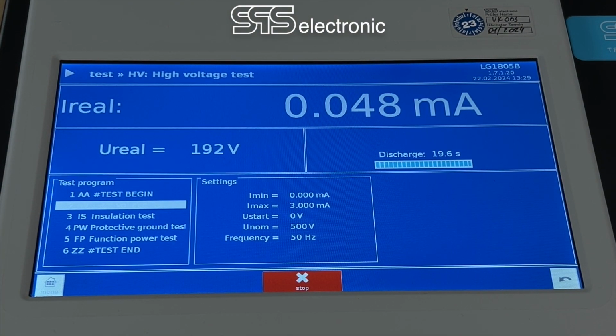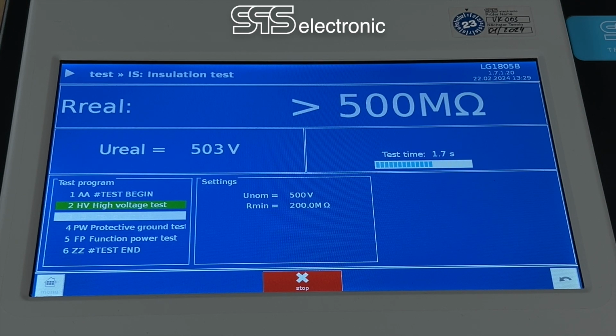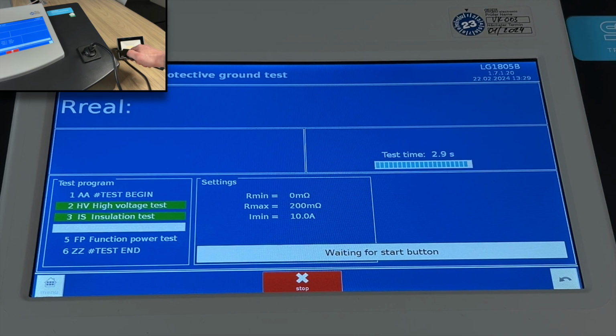Now we can see the measuring of the high voltage test, insulation test, protective ground test, which we start via the PE probe, and last, the function power test, when we can see our DUT light up.